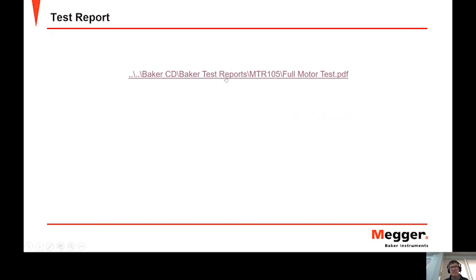Let's have a look at a typical test report. So you can change your logo. You can import a logo and replace Megger. You have your nameplate data, so you can maybe have a customer name, location of the equipment, that sort of thing. And then we get down to our test results. So we have our winding resistance tests, 46.8, 46.9, and 49.3 ohms. We have our direction of rotation, L123. We have our IR tests. So we did the temperature compensated test at 500 volts. We had 28 gig ohms at 25.5 degrees, and we had only 14 gig ohms at 40 degrees. So that is the corrected value.